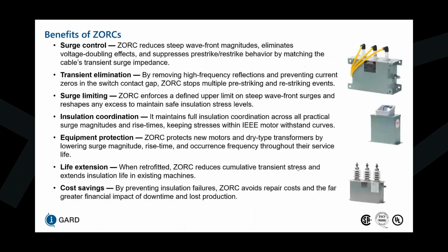So the benefits of the ZORC is that it has surge control. So ZORC reduces steep wavefront magnitudes, eliminating voltage doubling effects, and suppresses pre-strike and restrike behavior by matching the cable's transient surge impedance. There's transient elimination by removing high-frequency reflections and preventing current zeros in the switch contact gap. ZORC stops multiple pre-striking and restriking events.